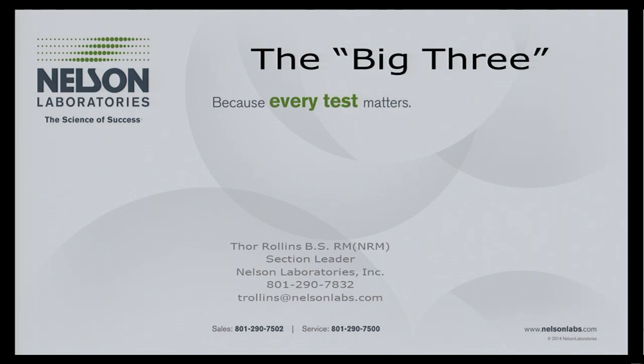Welcome everybody, and thank you for joining me today. We're talking about biocompatibility, specifically with the 'big three' tests. For those who don't know what the big three are, I have the ISO 10993 chart in slide rule form. As you slide through it, the three first tests — cytotoxicity, sensitization, and irritation — are marked on every single device category.